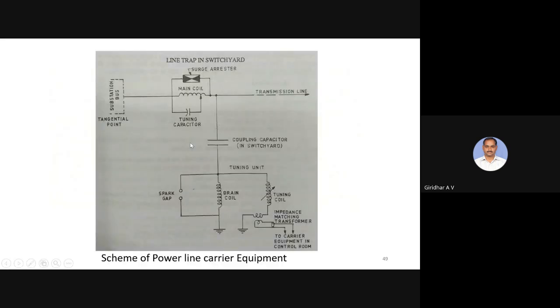So if you could see these power line carrier equipment. Usually power line communications we can use for voice communications, telemetry, telecontrol, SCADA purposes, like that different purposes we are using this power line carrier communication. Usually these carrier currents are in the frequency range of 30 to 500 kilohertz for the communication between two substations. If you want, through the transmission line itself, we can do this at higher frequencies. In that way, you will be getting the information between the substations through the transmission line, at 30 to 500 kilohertz frequencies.